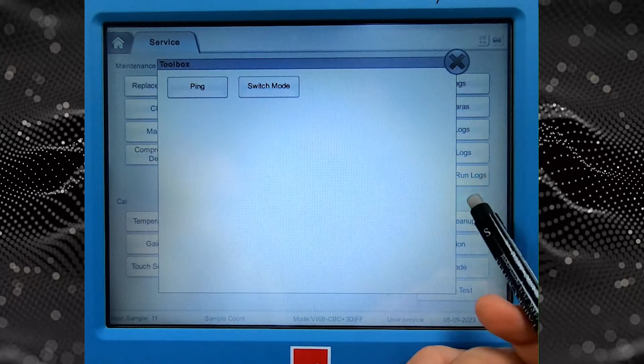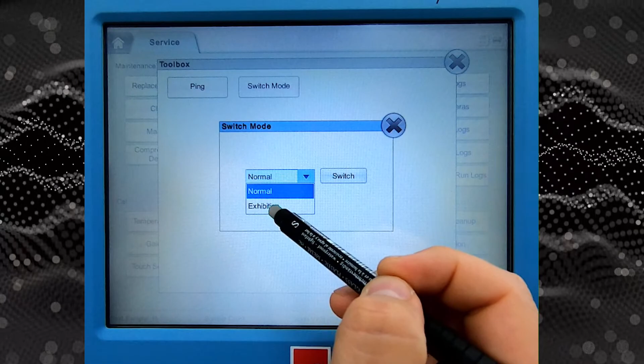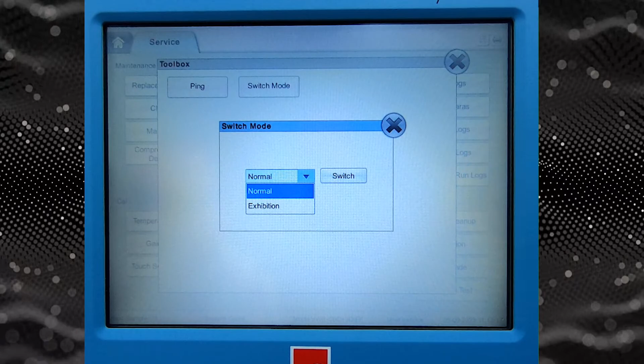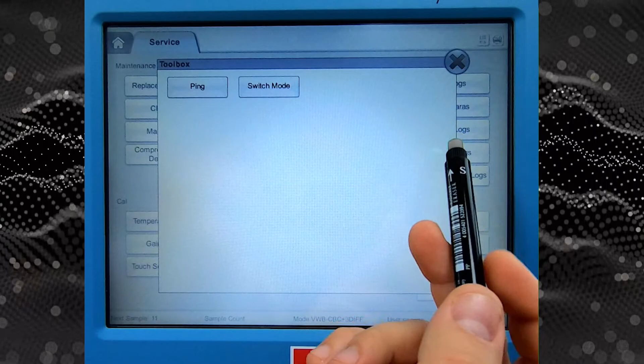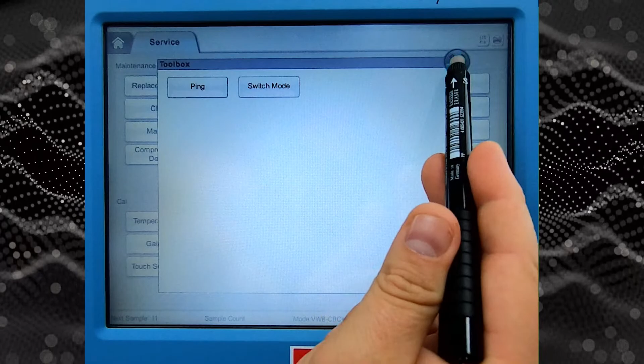In the toolbox, one thing which can be useful is this switch mode, and you can change it to exhibition mode. So actually, when the device is in the exhibition mode, the device will not use any reagents. It will not prime itself. The fluidic system will not be initialized. And actually, this is for, as the name suggests, the exhibition. So if you want to show this analyzer to customers, you can use this analyzer in such a mode, and you don't need to have any reagents connected. But for normal operation, you need to be in the normal mode.